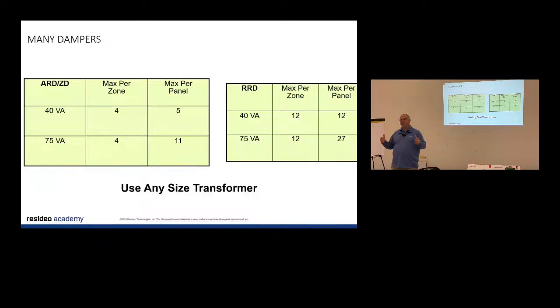We can do retrofit, and this is your biggest opportunity because they're obviously not building near as many houses as what they're retrofitting nowadays, right? And what a retrofit is: you've got your ductwork, and if you go down your basement, you've got 6-inch runs all the way off your ductwork, and you're doing your basement a little bit and upstairs a little bit. You can actually take each duct, so let's say in a typical ranch house, probably 8 to 10 upstairs and 6 to 8 down, and you just cut a hole in them, you slide our damper in there, and then you tie those all together.